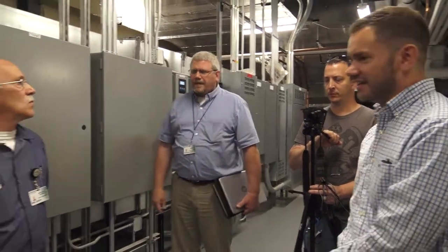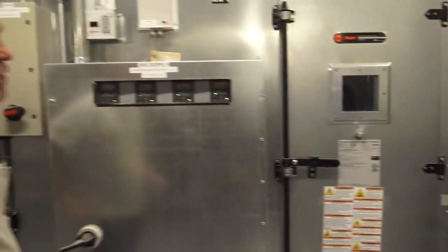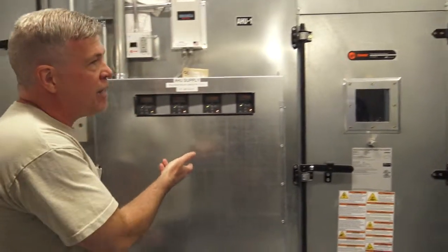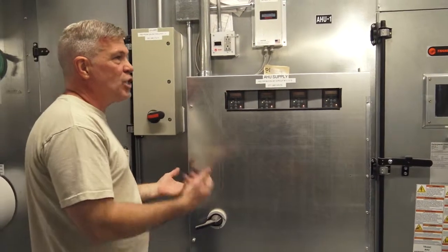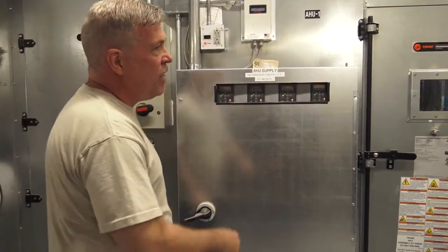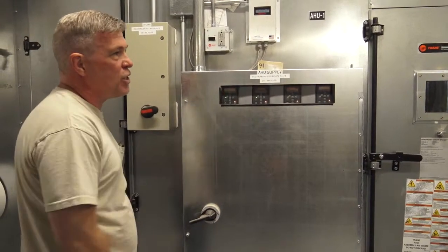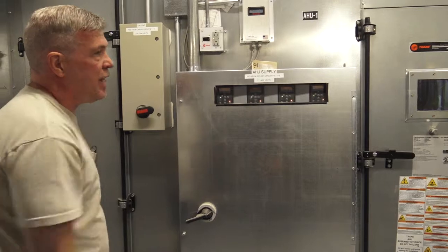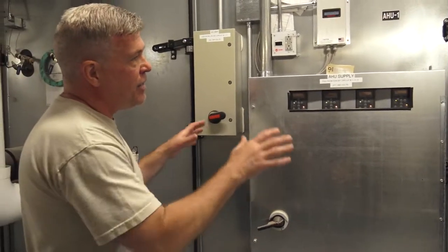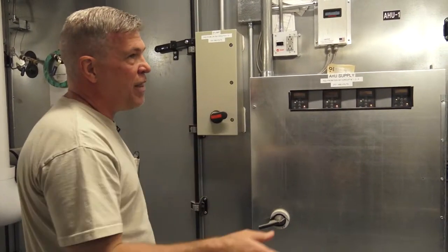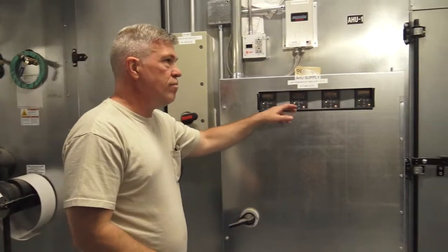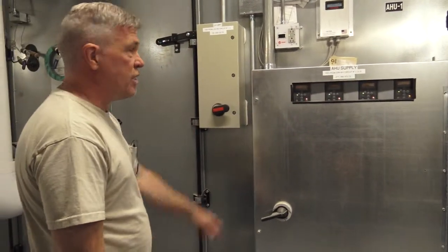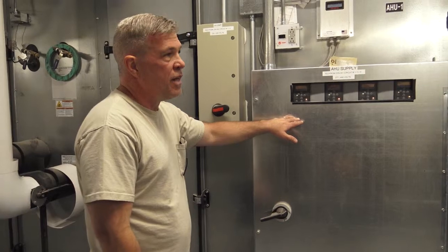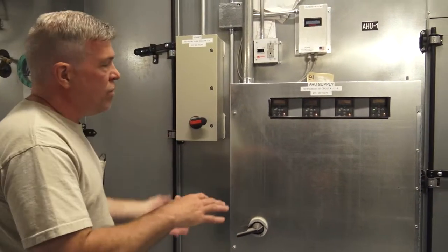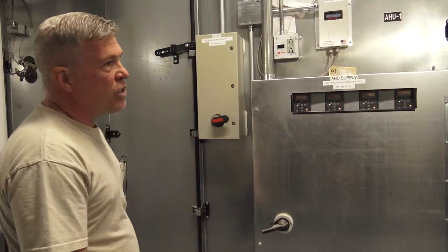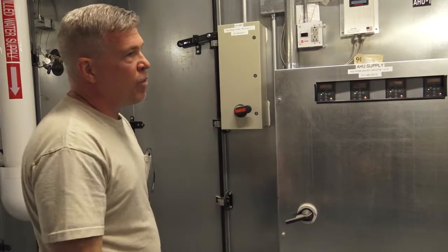The other thing you could do in that situation would be to somehow try to block off the fan so it just can't spin, because even if you shut the drive off, the air pulling through it is going to cause it to spin. I've seen that on one of these already. It still produces enough air to supply the building, but you'll definitely know it's not functioning like it should, because these will run at like 100% then, where normally they're around 50, 60 hertz. They'll be at 100, trying to make up for it running in the wrong direction.